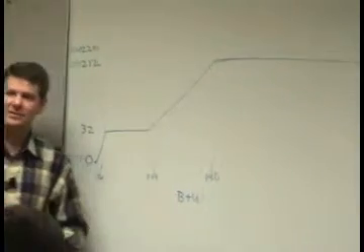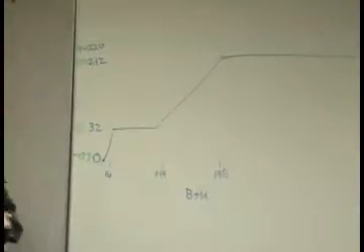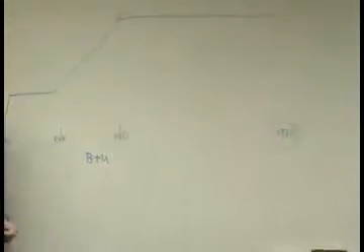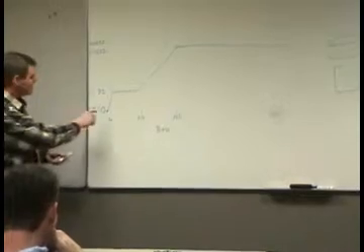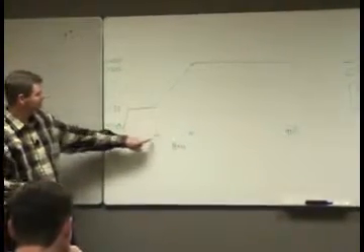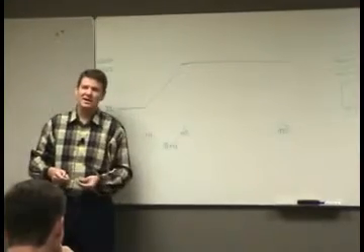And since we're at sea level, that's our boiling point. When we start adding more heat to that 212 degree water, it's going to start boiling. So here again, our line goes horizontal again, and we have to add 970 BTUs to that water to get it from 212 degree water to 1 pound of steam. So as you can see, our sensible heat here was not a lot of BTUs really in the big picture, but our latent heat to get it from water to steam was a lot. That 970 BTUs is a lot of heat to get it completely vaporized so we're completely into steam.